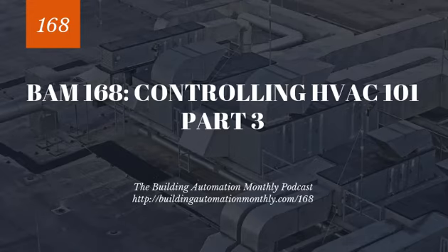And if you can have that lower, then you don't have to transfer as much heat to cool the leaving water. I mean, that makes sense, right? Because if the chilled water return temp is closer to the chilled water supply temp set point, then you're going to have to run the compressor less to kind of get that heat over to the condenser side where it can be evaporated by the cooling tower.